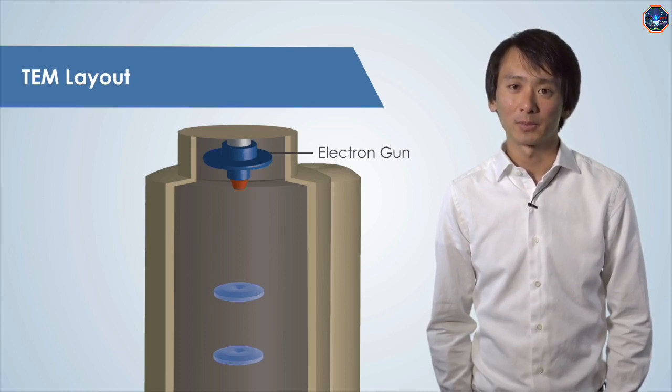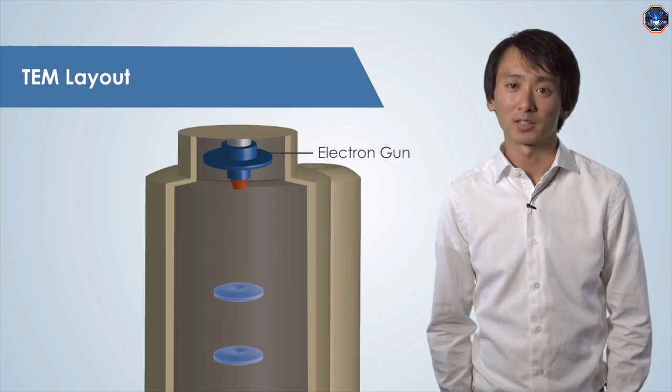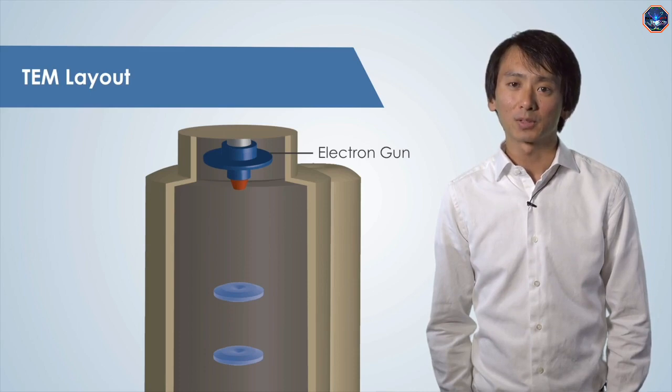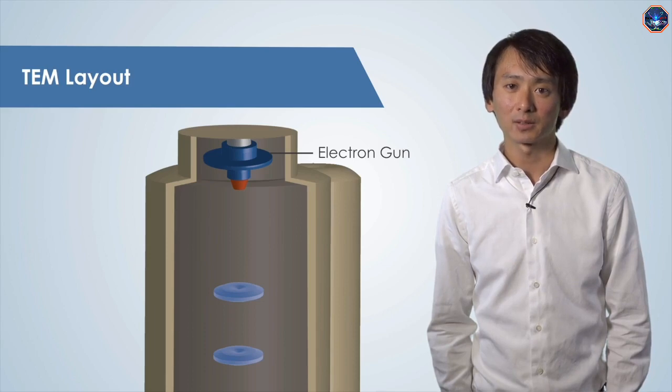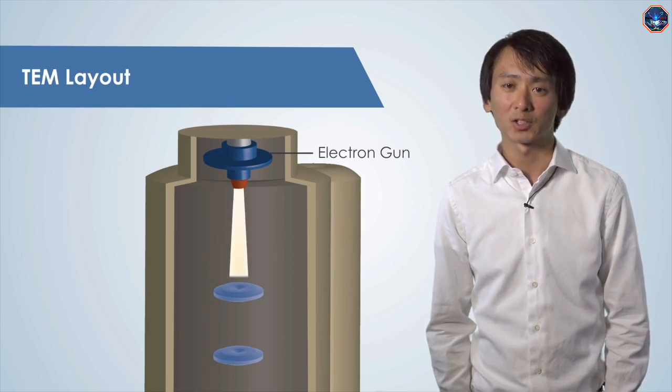Field emission guns use a sharp, typically tungsten tip as an emitter with an applied voltage to extract electrons. This emitter generates more electrons than traditional thermionic emission guns. Both emission types have an anode located below the filament. The electrons accelerate from the cathode toward the anode to create an electron beam.